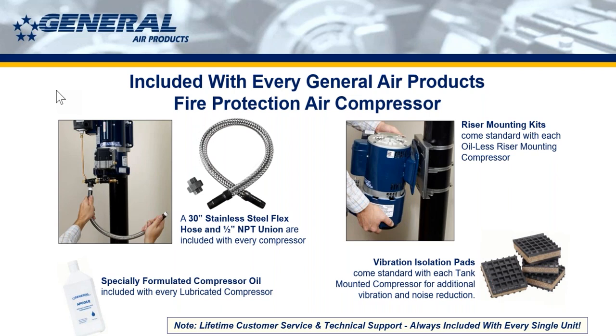Additionally, we have the specially formulated compressor oil. It's either 30 weight or 40 weight non-detergent. You just have to call us, because it depends on which unit, to get the right oil. So if you need oil replacement, you can order the oil from us, or you can go to your local AutoZone or whatever and pick it up. But just make sure you give us a ring and find out what the right one is.